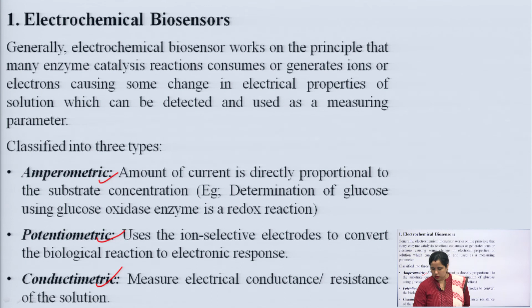So, these are biosensors which are measuring the analyte in your sample. The amperometric type of biosensor determines the concentration by identifying the current, which is directly proportional to the substrate concentration, right. Potentiometric uses ion selective electrodes to convert the biological reaction to electronic responses. These all are the same, measuring the component values in the sample, but using different approaches. Conductimetric measures the electrical conductance or resistance of the solutions, right. So, this is how an electrochemical biosensor works.